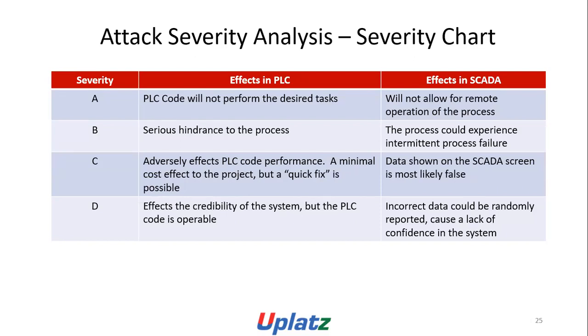Severity level A, effects in PLC: the PLC code will not perform the desired task. Effects in SCADA: it will not allow for remote operation of the process. Severity B, effects in PLC: serious interruption to the process. Effects in SCADA: the process could experience intermittent process failure. Severity C adversely affects PLC code performance, with a minimal cost effect to the project, and a quick fix is possible. Effects in SCADA: data shown on the SCADA screen is most likely false. Severity D affects the credibility of the system, but the PLC code is operable. Incorrect data could be randomly reported, causing a lack of confidence in the system.